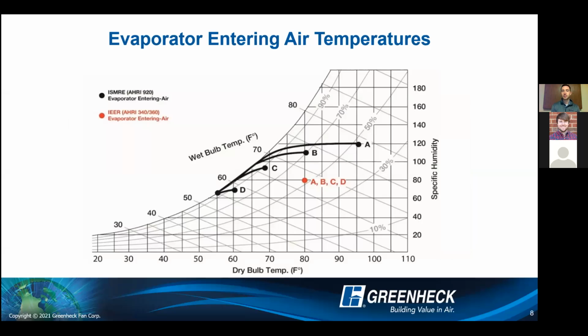Again, I'm going to break it down on a psych chart so you can really paint that picture. But you see that the point in red, that is the ABCD, that is every condition, no matter what, that is the entering air temp into the evaporator. So it's going to be pretty consistent from a capacity standpoint and from an efficiency standpoint. When you look at the ISMRE, now you can see there is a whole wide range of conditions, and that really indicates that 100% outdoor air. So, you know, in the Georgia area, you can have days that are extremely hot, but maybe not as humid, or you can have days that are a little bit cooler, but they're going to have a high amount of moisture in the air, where in these applications where you're using this DOAS type equipment, you're definitely going to want to make sure that we're stripping out moisture. And that is really the efficiency value that we're going to want to care about.